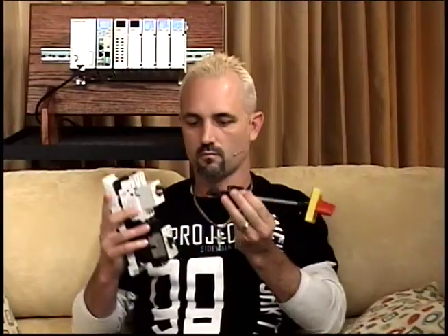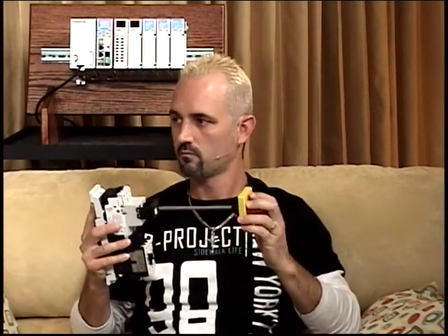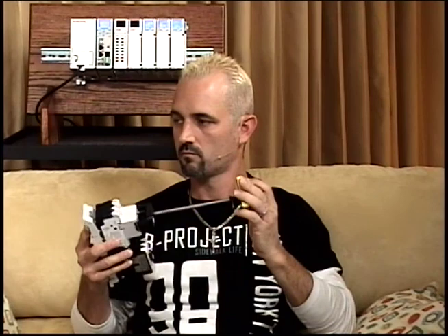These are sold in different current ranges. I think we carry two different sizes, a 45 millimeter and a 55 millimeter. They're available to control up to 60 horsepower at 600 volts AC. There are rotary handles and on-off trip indicators on the front of it. So I can actually attach one of these through my enclosure, right? Yep, so I can turn it on and off.